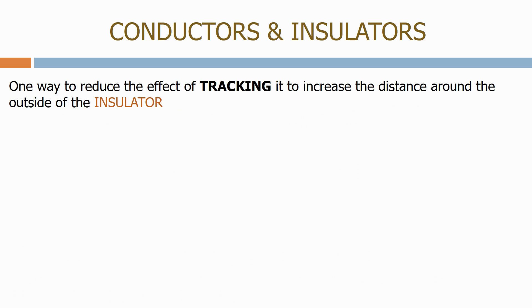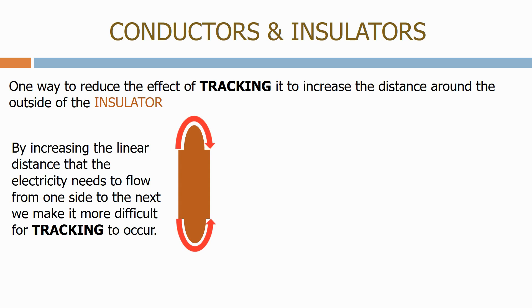One way to reduce the effect of tracking is to increase the distance around the outside of the insulator. By increasing the linear distance that the electricity needs to flow from one side to the next, we make it more difficult for tracking to occur.